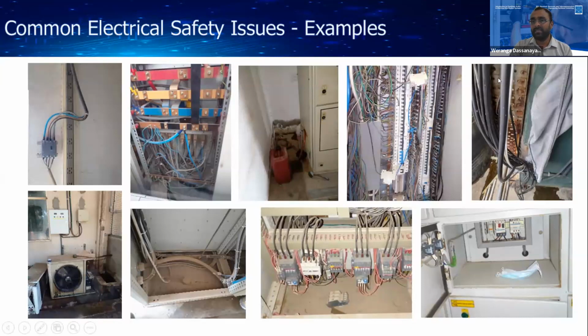The cables are hanging from top to bottom. There is no support for the cable, so the cable can get tension. It's like this, the insulation is damaged. So when you are doing this kind of audit, you have to see, record and take photographs of this kind of damaged insulation. It is a must during a condition audit.